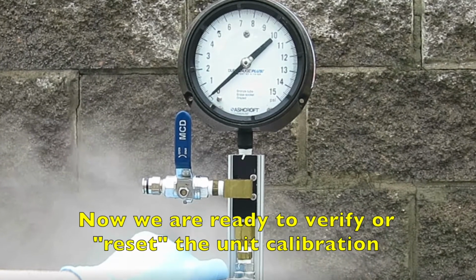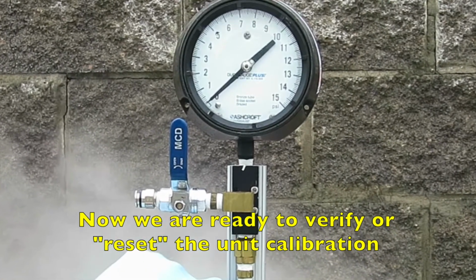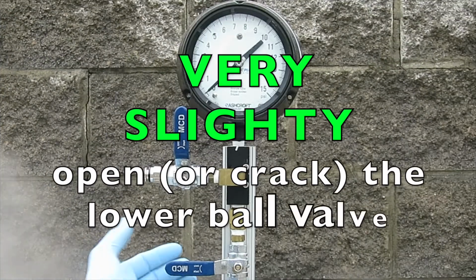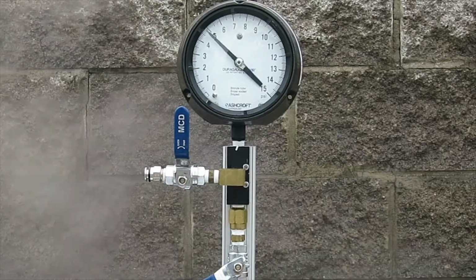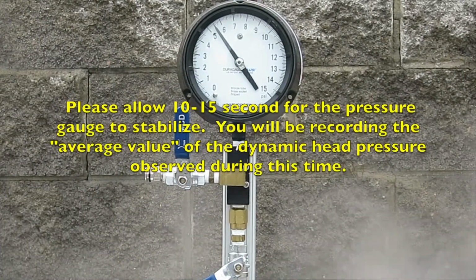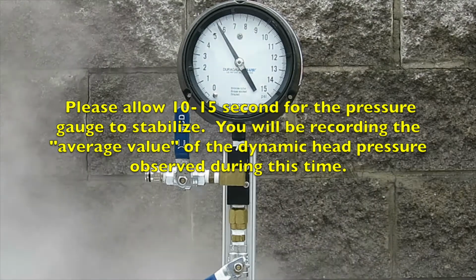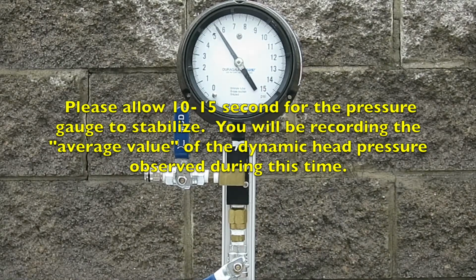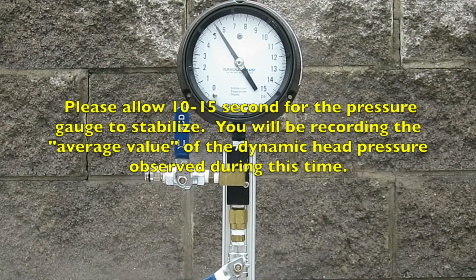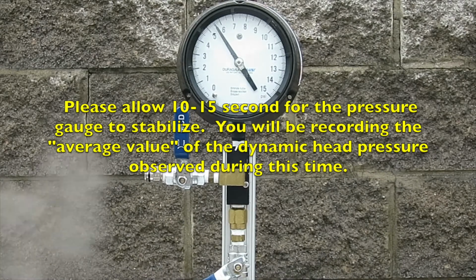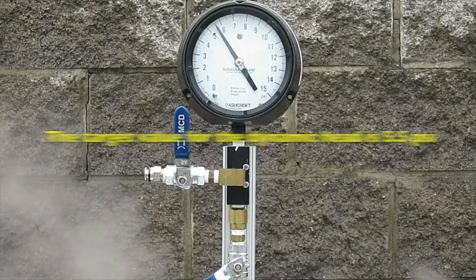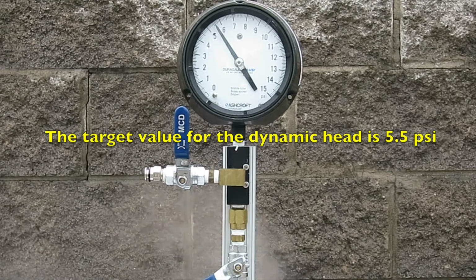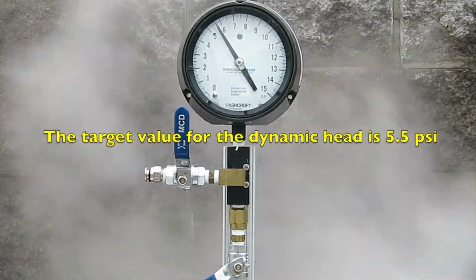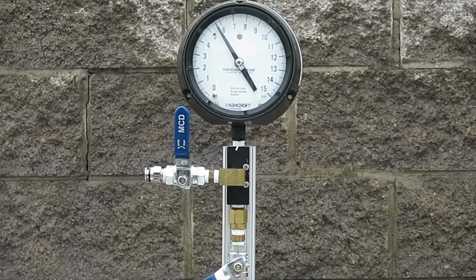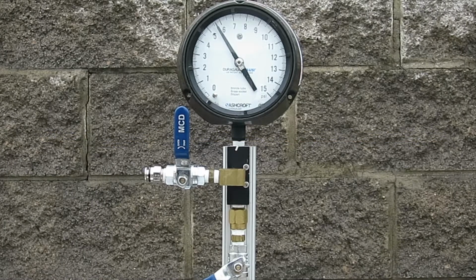Now, we are ready to verify or reset the unit calibration. You are going to very slightly open the lower ball valve. This will help to control the stability of the gauge needle. Please allow 10 to 15 seconds for the pressure gauge to stabilize. You will be recording the average value of the dynamic head pressure observed during this time. The target value for the dynamic head is 5.5 psi. It might be helpful to place an extra fine permanent mark on your gauge representing the target of 5.5 psi.